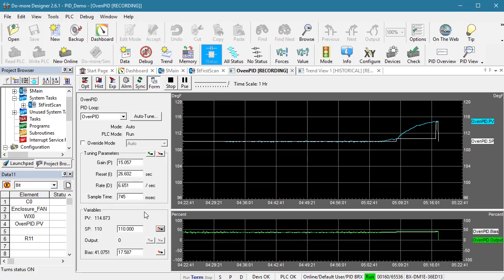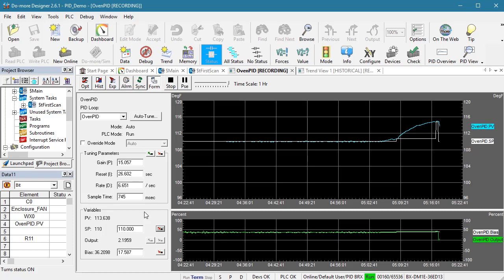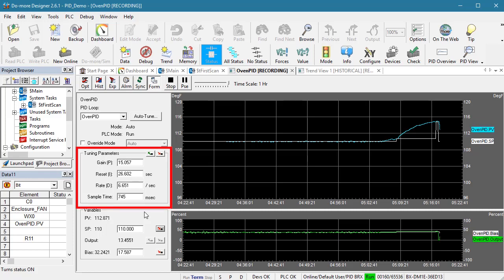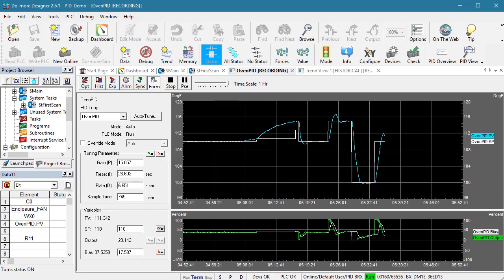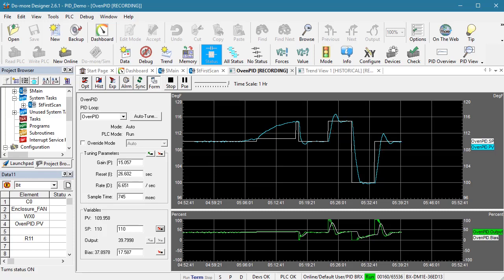That's it. That's the whole open loop Auto-Tune cycle. It's just a single bump exactly like we did in our manual tuning. There is no 3 cycle stuff like we are used to seeing in the closed loop Auto-Tune. Our new coefficients and new sample time are automatically populated, so let's fast forward through our standard setpoints. Looks good. It's got a 1.5 degree overshoot on the upswing and a near perfect landing on the downward run. Nice.